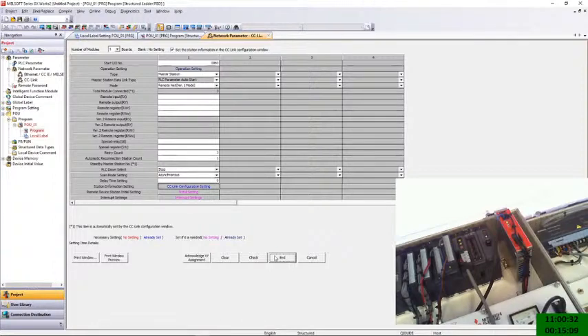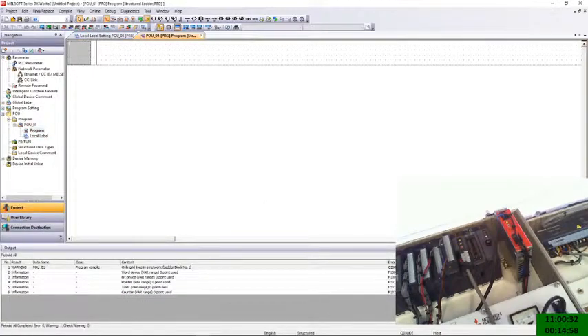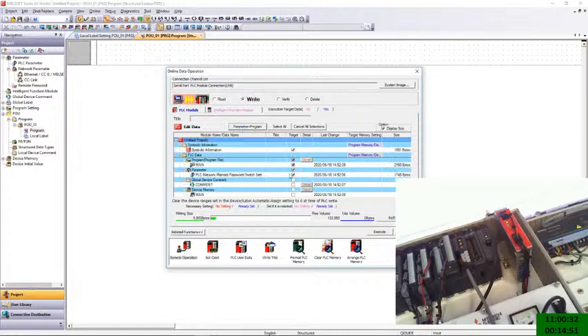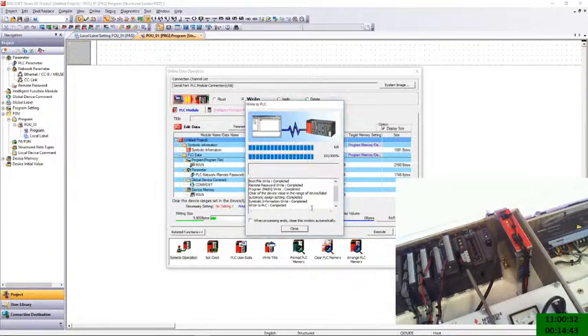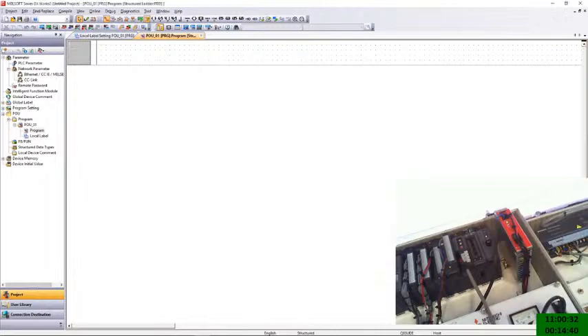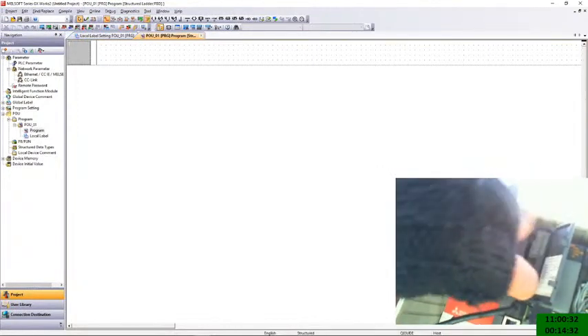Then I compiled by doing Rebuild All. It compiles the program — no errors found, just a small warning because the program was empty. Then I wrote the parameters and program to the PLC. Once done, I put the PLC into run mode — no errors. You can then see the SD and RD LEDs on the slave devices come on and stay solid, confirming that communications to those devices are established.